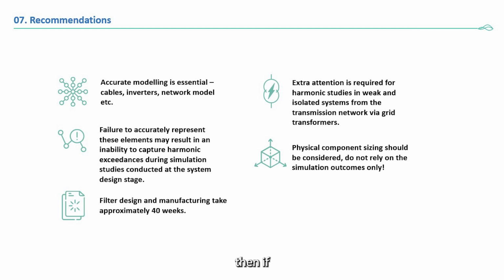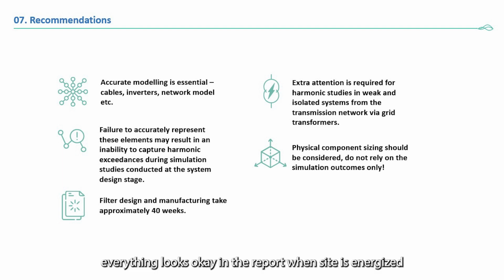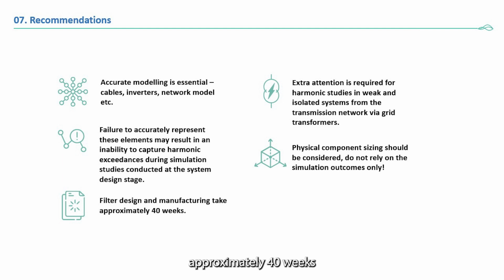Then, if these components are not modeled correctly, everything looks okay in the report. When site is energized, if non-compliance is captured at site, to receive a final acceptance from DNO, it takes time, and it means that this is a potential project delay, because nowadays manufacturing and design process takes approximately 40 weeks. And most importantly, we have experienced that some of the clients do not have enough space for harmonic filter footprint. So if it is not planned at early stage, there can be potential project delays later. And especially if system is weak, extra attention is required for harmonic studies.